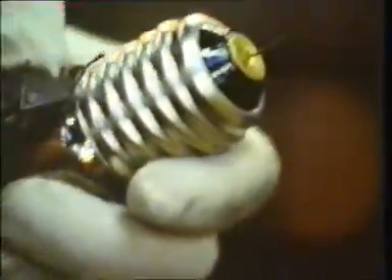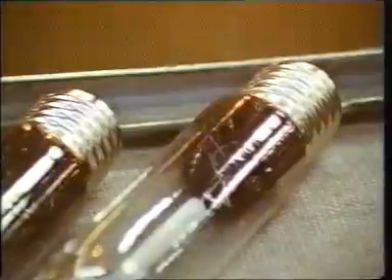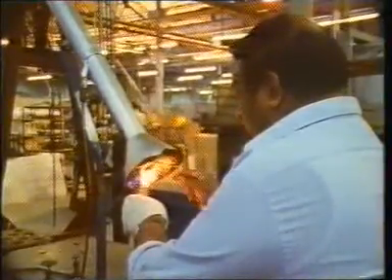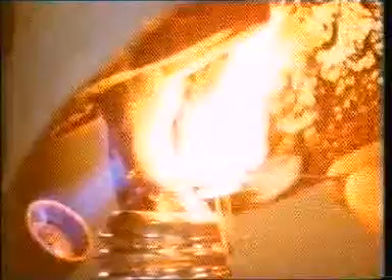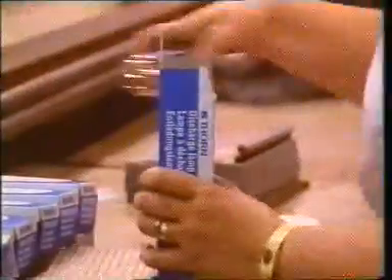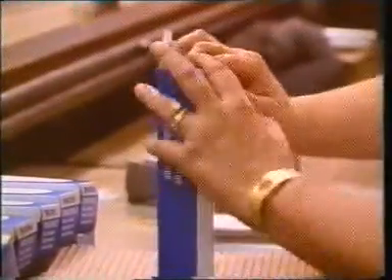Most domestic incandescent lamps have a life expectancy of 1,000 or perhaps 2,000 hours. Nowadays in the industry we talk about the life expectancy of high pressure discharge lamps like the high pressure sodium lamp in terms of a survival curve. 50% survival at 24,000 hours is a typical value for a high pressure sodium lamp. 24,000 hours, of course, is some 3 years or more of continuous operation, so we're talking about a very long-lived product here.